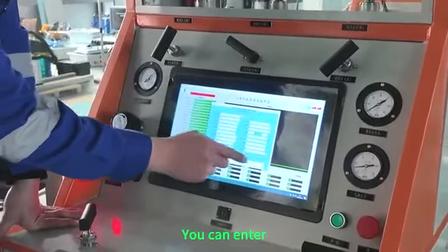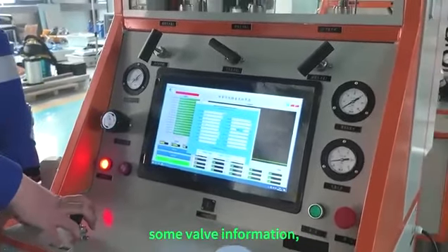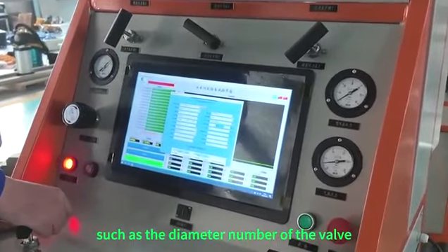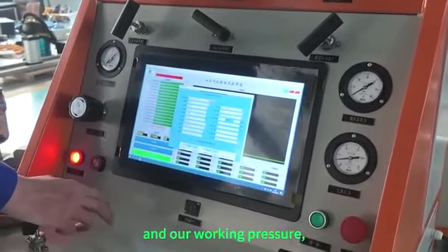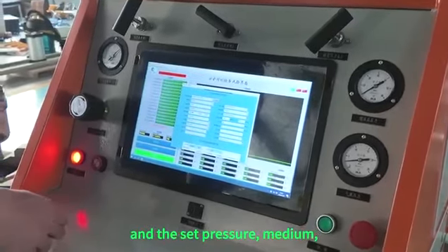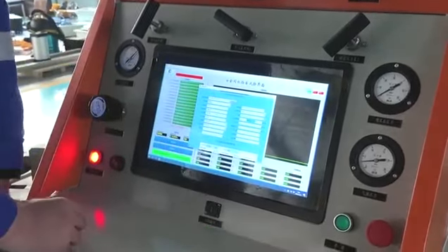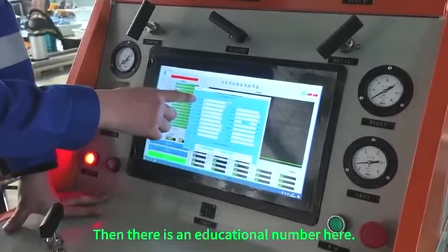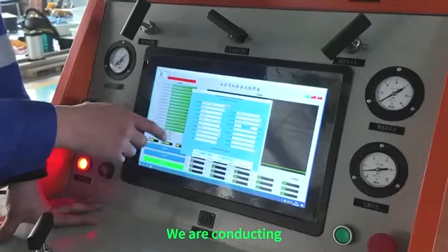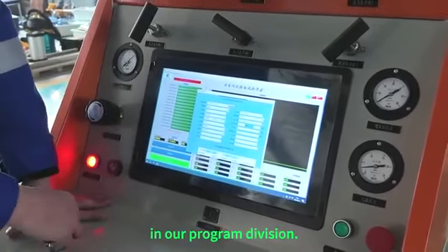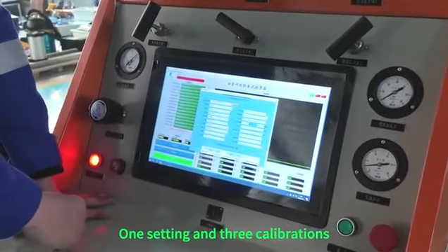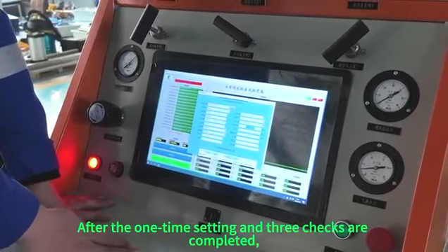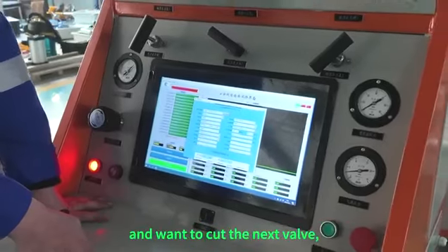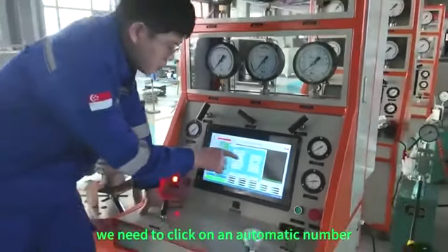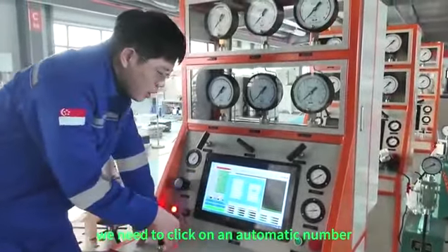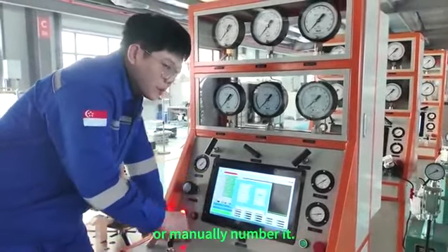You can enter some valve information, such as the diameter number of the valve, our working pressure, the set pressure, and the medium, which can be set here. Then there is a number here. In our program, we conduct 1 setting and 3 calibrations. After the 1 setting and 3 checks are completed, if you want to switch to the next valve, you need to click on automatic numbering, or number it manually.